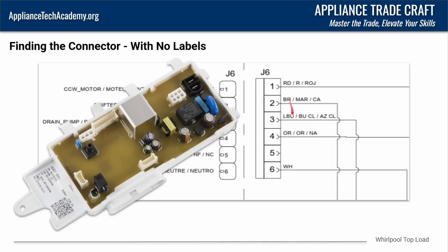And what you can also do is compare the wire colors. Now, one other thing that I have seen is techs get confused. Oh, it says white right here, but I have a black wire there. Or this one has a black wire with a white tracer, but I'm seeing a white wire. It's not lining up. Well, if all the other ones line up, and that's the only connector, then clearly that's going to be your connector. Most of the time I see this one being different. These are generally all the same on these units. But just throwing that out there, it's really a process of elimination. Don't get confused or scared if you're not entirely sure because it doesn't say right there J6. It's a process of elimination.